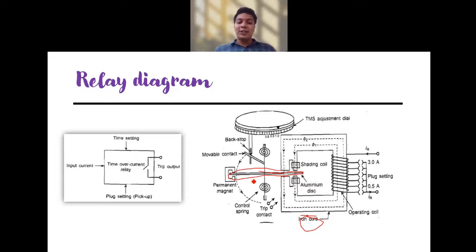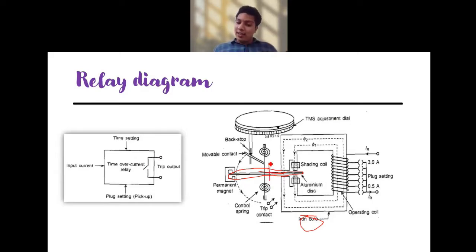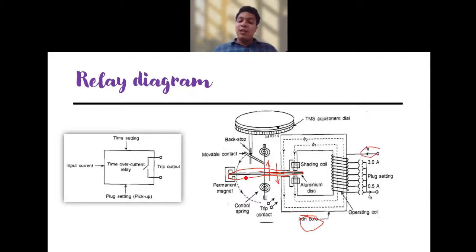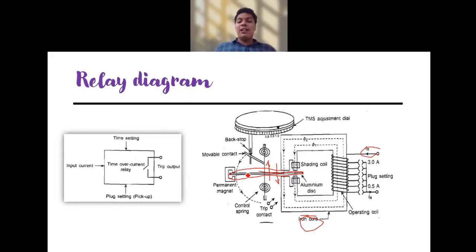There will be a change in magnetic flux linkage, so on the disc there will be two forces. Whenever the magnetic flux linkages change, there is current formation in the aluminum disc, and there will be two currents producing a force that is not in equilibrium. There will be a net force particularly when you have a high amount of current, and due to that force the aluminum disc will rotate - that rotation causes a deflecting torque.